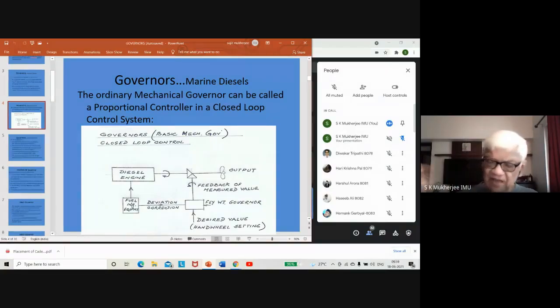Now, ultimately, the governor, what is it doing? It is controlling the fuel racks. Similarly, in the Sulzer pump, it is controlling the rack, which is going to control the position of the eccentric to make that lever work as desired. So that is the other side of the story. Right now, we'll stick to our governor function. So once the signal comes to the fuel injection system, it will increase or decrease the fuel, and thereby you will get a change in the RPM.